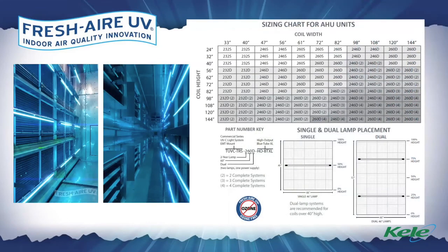We try to make sizing really, really simple. On the BTXL spec sheet, we have this cross-reference matrix on sizing. You just line up the width and height of the coil, and that'll tell you how many fixtures you're going to need. In the example in the bottom right corner, for a 40 inch high by 48 inch wide coil, it'd be one single UV lamp. Typically for coil disinfection, it's one lamp every 30 to 40 inches.